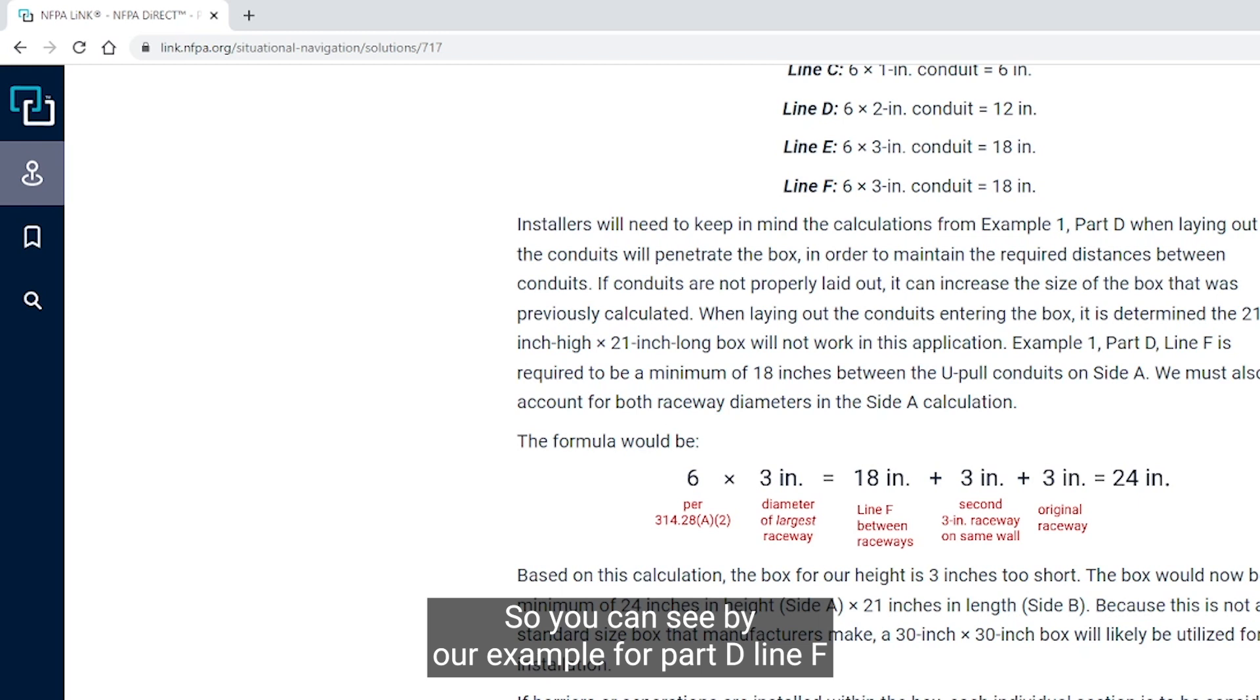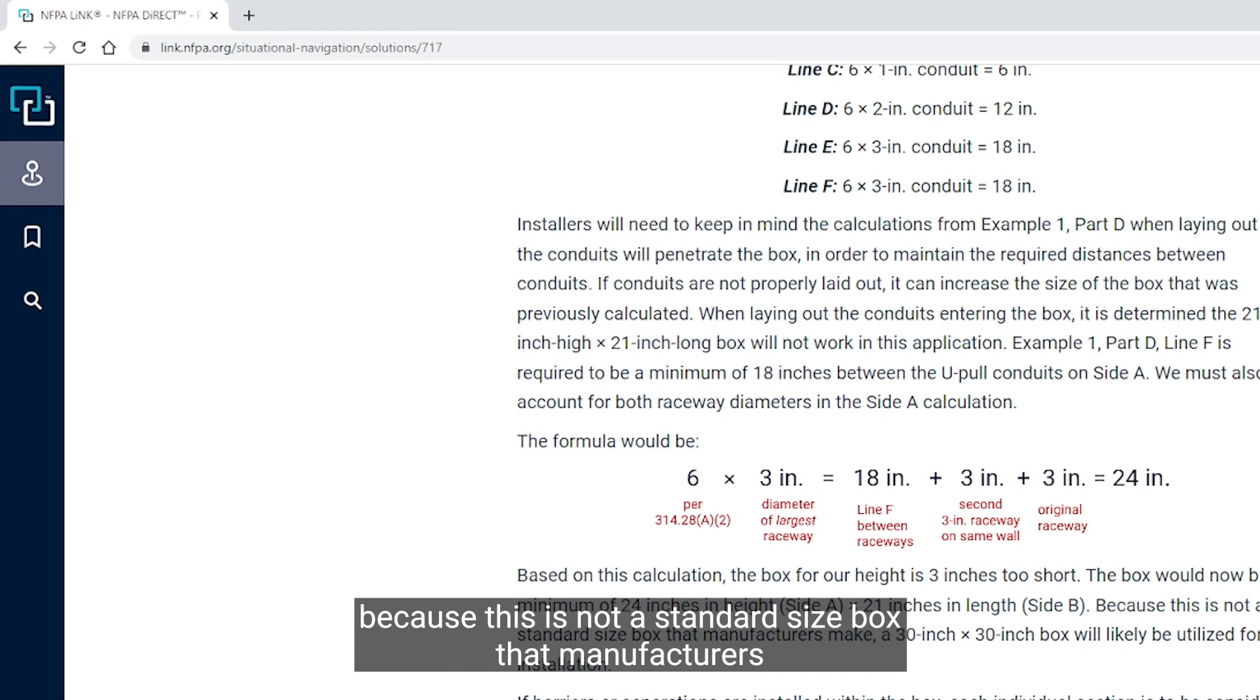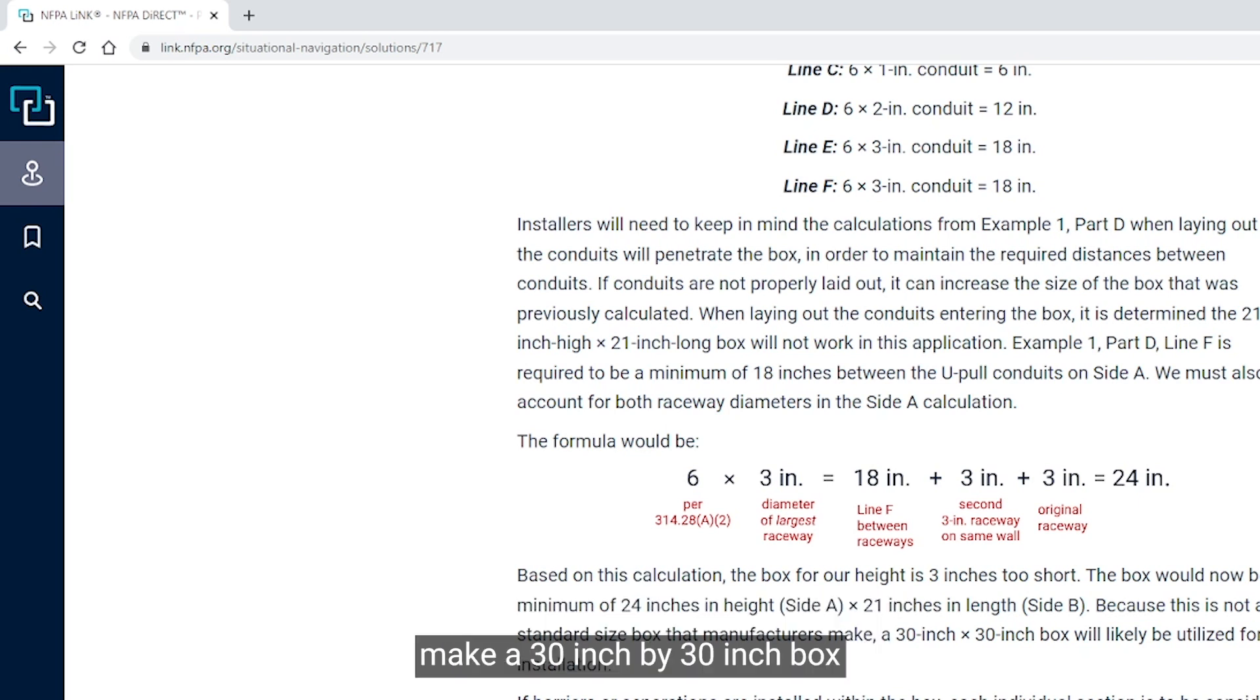So you can see by our example for Part D, line F, the 21 by 21 inch box will not work. You will see that it's 3 inches too short. So this box would now need to be a minimum of 24 inches on side A and 21 inches minimally on side B. Because this is not a standard size box that manufacturers make, a 30-inch by 30-inch box will likely be used for this installation.